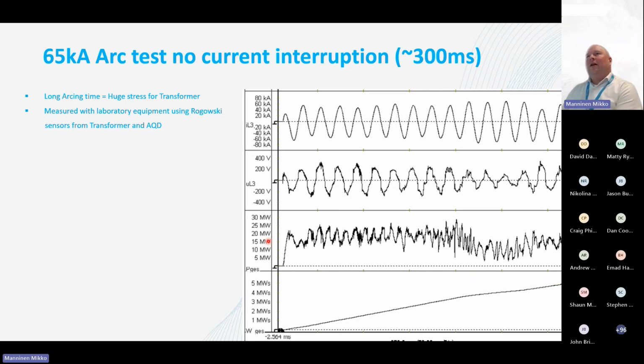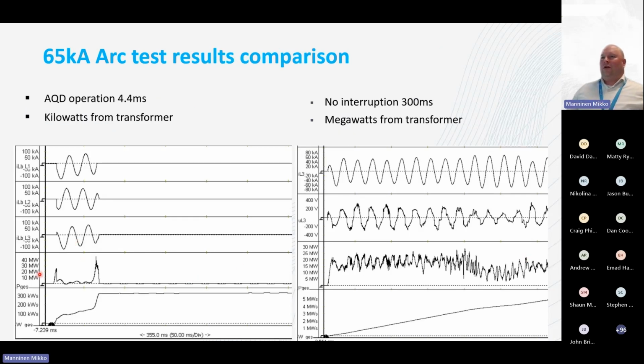Of course, like you saw in the first test with 30 kiloamps, we actually lost most of the copper from inside the panel. It vaporized completely already with 30 kiloamps. So this is 65. So when you see changes here, the copper is practically already gone. And the explosion and arc flash keeps going until you lose the energy to feed the fault. And then we can also do the comparison with the arc fencing on the left side and without the arc fencing on the right side. So it is a significant difference when it comes to the incident energy ratings. 300 kilowatts versus 5 megawatts.